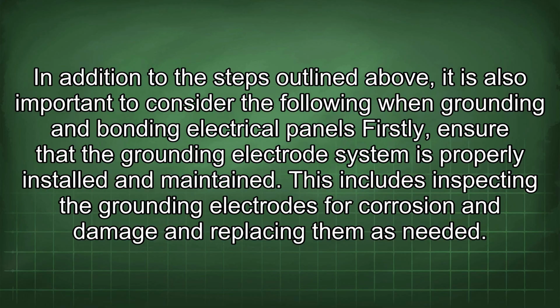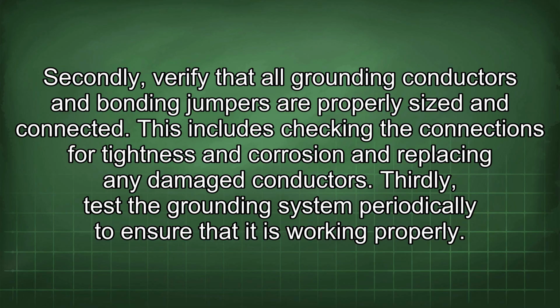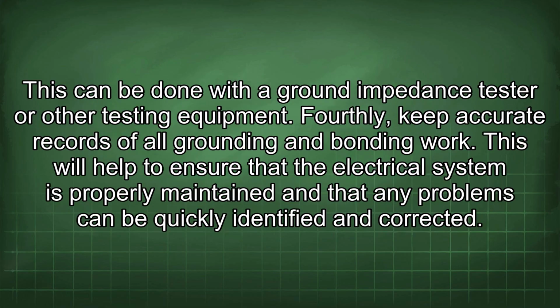This includes inspecting the grounding electrodes for corrosion and damage and replacing them as needed. Secondly, verify that all grounding conductors and bonding jumpers are properly sized and connected. This includes checking the connections for tightness and corrosion and replacing any damaged conductors. Thirdly, test the grounding system periodically to ensure that it is working properly. This can be done with a ground impedance tester or other testing equipment.